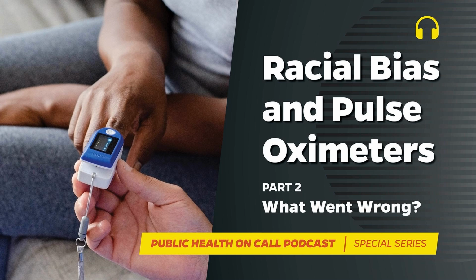At any point over the last 4 decades, when research began to reveal these biases, manufacturers could have changed the technology to fix it. After all, manufacturers are tweaking and putting out new devices and bug fixes all the time. But when it comes to accounting for skin tone, by and large, pulse oximeters haven't changed much since that Nellcor design from the 1980s that was designed and calibrated for lighter skin tones.